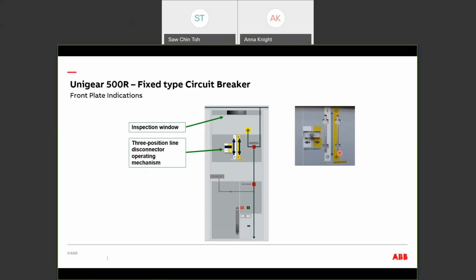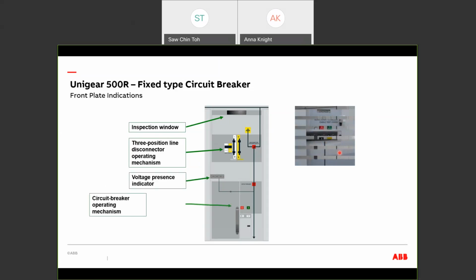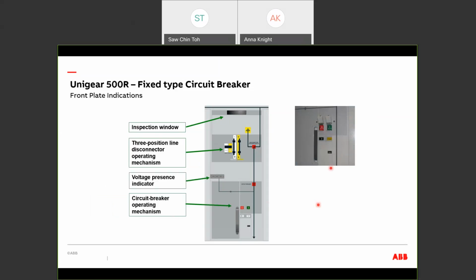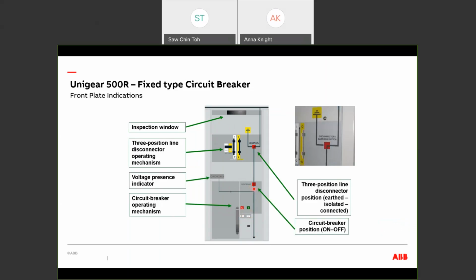Next, we have the voltage indicators. The circuit breaker operating mechanism is also at the front of the cubicle. You can open the circuit breaker, close it, and also charge it from the front of the panel. The panels come with a mimic, and on the mimic you have the circuit breaker on-off position indicators, as well as the three position switch position indicators.